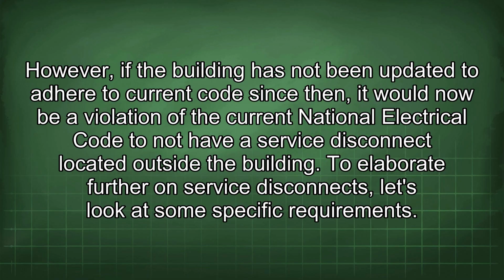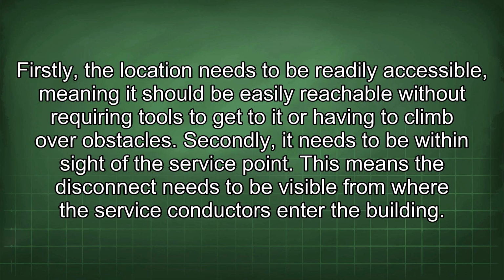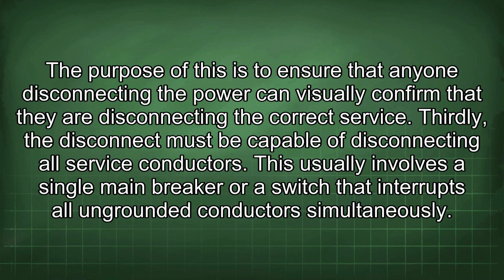To elaborate further on service disconnects, let's look at some specific requirements. Firstly, the location needs to be readily accessible, meaning it should be easily reachable without requiring tools to get to it or having to climb over obstacles. Secondly, it needs to be within sight of the service point. This means the disconnect needs to be visible from where the service conductors enter the building. The purpose of this is to ensure that anyone disconnecting the power can visually confirm that they are disconnecting the correct service. Thirdly, the disconnect must be capable of disconnecting all service conductors. This usually involves a single main breaker or a switch that interrupts all ungrounded conductors simultaneously.